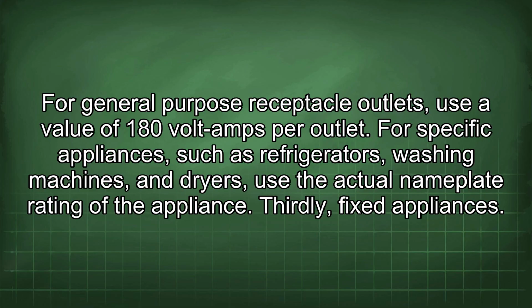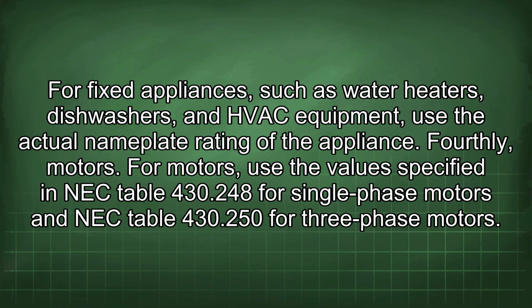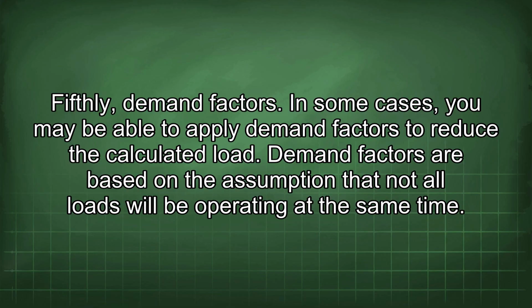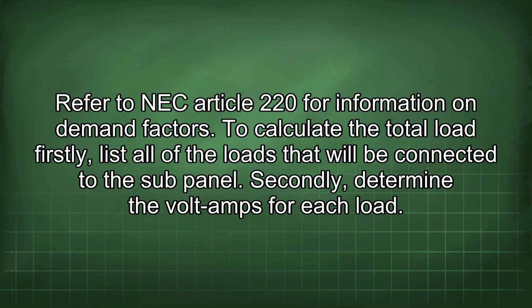Thirdly, fixed appliances. For fixed appliances, such as water heaters, dishwashers, and HVAC equipment, use the actual nameplate rating of the appliance. Fourthly, motors. For motors, use the value specified in NEC Table 430.248 for single-phase motors and NEC Table 430.250 for three-phase motors. Fifthly, demand factors. In some cases, you may be able to apply demand factors to reduce the calculated load. Demand factors are based on the assumption that not all loads will be operating at the same time. Refer to NEC Article 220 for information on demand factors.